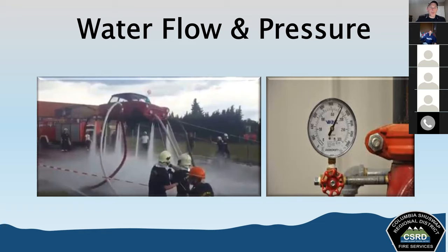And then there's a concept called residual pressure. Residual pressure is the pressure remaining in the system when the water is flowing. It decreases more as the water flows. So as the water flows, residual pressure goes down, and when the water stops, residual pressure will increase.